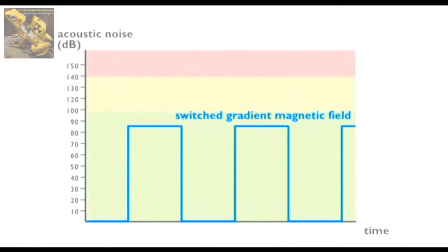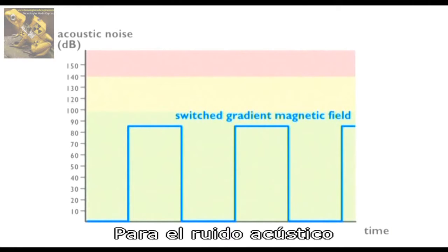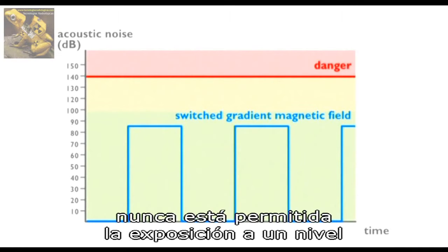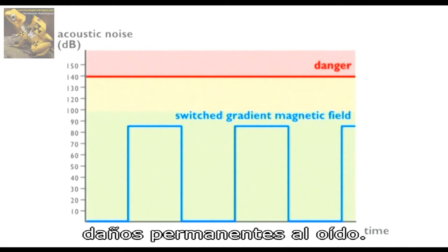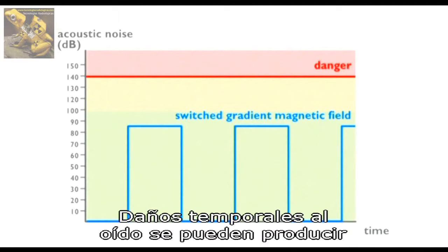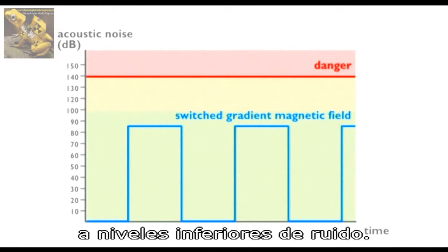For acoustic noise, exposure to a level higher than 140 dB peak noise is never allowed, to prevent permanent damage to hearing. Temporary hearing damage can occur at lower noise levels.